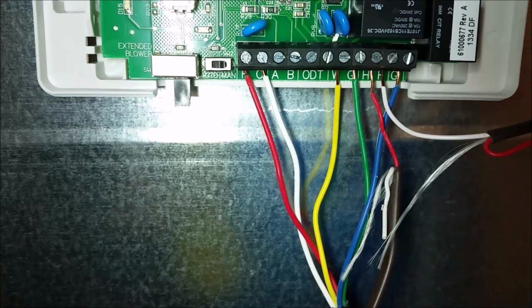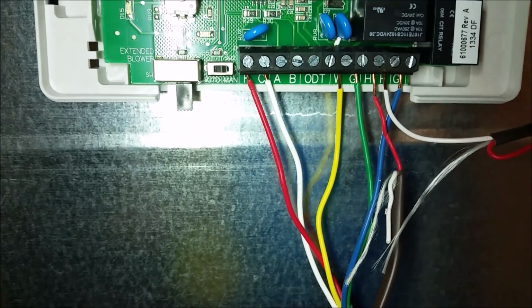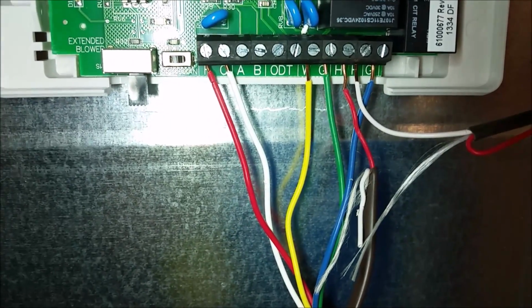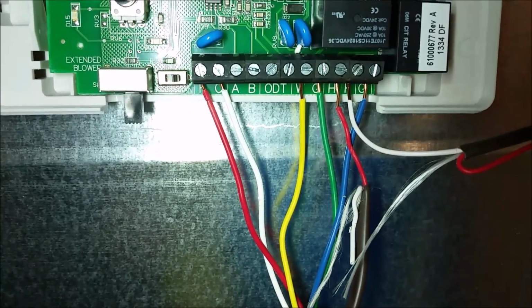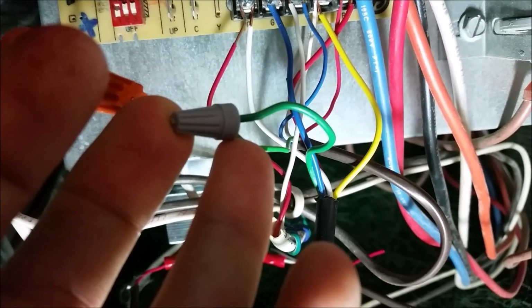Okay, the only other part that really tricked me with the wiring was the green wire, or the connection going to the G. You have a G and a GF. The G is an input port, and that is coming from your thermostat where you set the temperature. At first I thought, well, that's kind of silly. I don't want to have to run a cable all the way up to my thermostat. But after reading the small pamphlet, I understood that what it wanted you to do was to unhook the green wire, well, it may not be green in your case, but the G on your furnace, and then tie it into another low voltage wire and make that wire go to the G input on your humidity control.